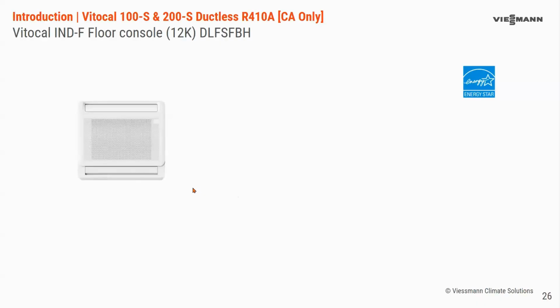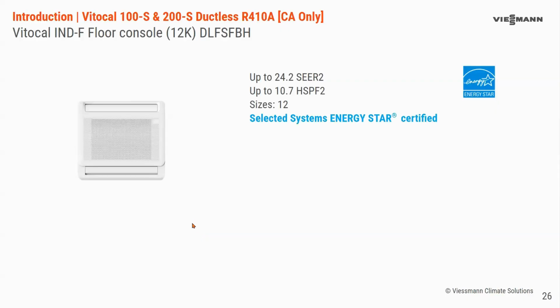So the next indoor unit is the floor console. This is specifically the 12K size. You'll see what I mean in the next slide. So this is a floor console only. What that means is it's not installed literally on the floor, but on the wall, slightly above the floor or floor standing on the wall, similar to an electric baseboard type of product.